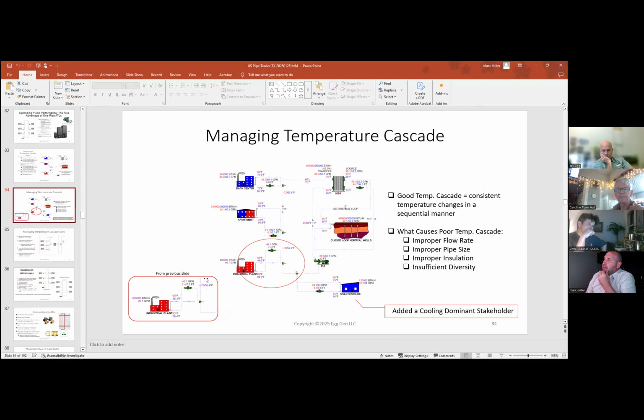So in our previous slide, remember our ambient temperature loop was 75 and 36. Well, now look what happens to our loop over here. We're at 78 and 54 because we added this cooling dominance. So this guy's dumping a bunch of heat on the loop. Now look at the inlet temperature. It's 69 degrees, okay? Whereas on the other slide, with less diversity, it's 56 degrees. So again, this proves that diversity, the more diversity, the better the system performs, all right? And as you go along, you can see progressively that the temperatures are increasing.